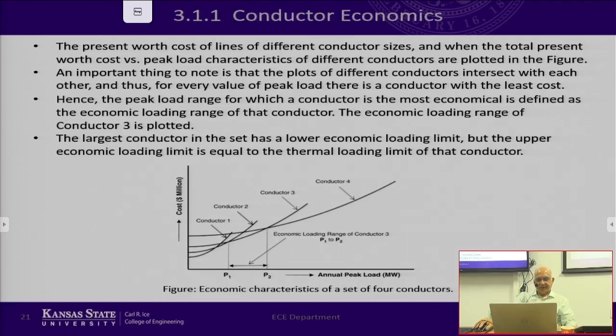Now, on the other hand, economic reach is defined by, for example, if you're looking at conductor number 3, it can carry power from P1 to P2. So the maximum power it will carry is P2. So the economic reach of this conductor is calculated based on P2, just the maximum P that you want to load with that particular size of conductor. That's what we call the economic reach.